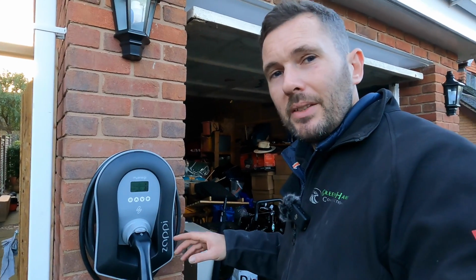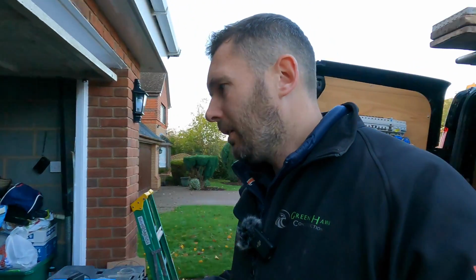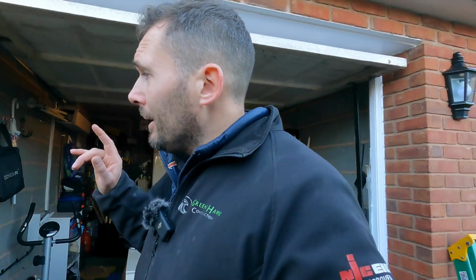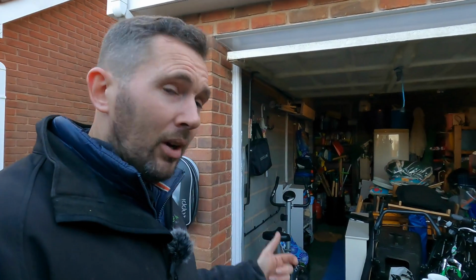We've changed all the settings, so we're out of the eco mode because we're not going to be charging on the off-peak settings on here. But it allows us then to grow. So if we do have solar and battery storage and things like that, we can whack that on there at a later date. The other thing to notice as well is, because I've now got 2 DBs, you need to label both of them, even though I'm not actually doing anything to the other one. But yeah, it's all tested out now. Nice low results.